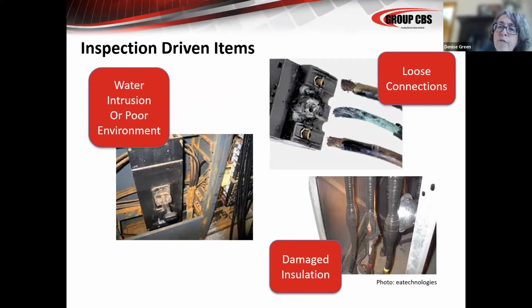So a lot of breaker issues can be found during just inspections. So the picture on the left, if you pull a panel off and everything is rusted, and you can see that all the metal at the bottom of the gear is rusted, the supports are rusted, that is an indication that, despite testing, you have a maintenance situation on your hands that could lead to an arc flash situation. The continual rise and fall of water and the deposit of rust and contaminants makes this a highly likely area for an arc flash situation to occur.